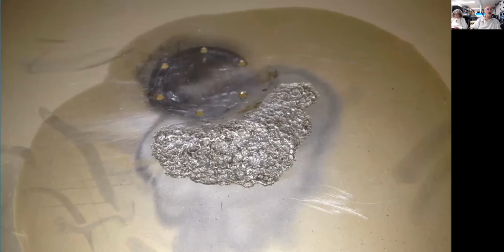That was on the bottom of the overhead section of that multi-section pi line, transmission line, or tuning matching network. That bolt pattern you see here is where there was actually a fixed vacuum capacitor, not a variable one. We figure at some point in the life of this transmitter they had a massive arc over of high voltage, which is around 15,000 to 17,000 volts at 15 amperes on those tubes. That's their plate supply per tube.